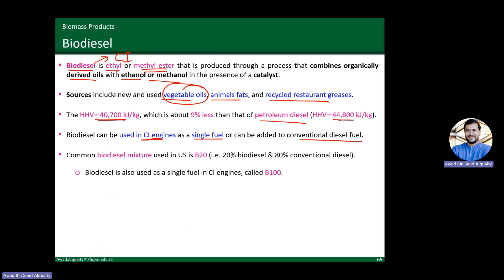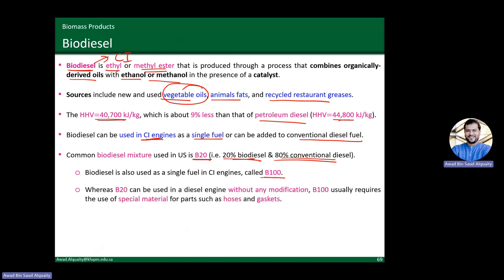Common biodiesel mixtures are B20 — 20% biodiesel and 80% conventional diesel — or B100, which is 100% biodiesel. With B20, no modifications to existing engines or fuel supply lines are needed. But with B100, you need to change hoses and gaskets, because biodiesel and other oxygenated biofuels tend to react with rubber and degrade it. You just need different materials in the fuel supply line — materials compatible with these oxygenated fuels rather than fossil diesel.